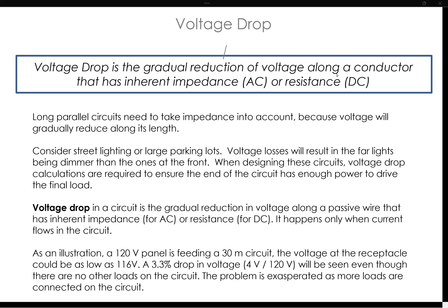Consider large parking lots, street lighting, or ballparks. These voltage losses — this voltage drop — is going to result in those lights that are really far away being dimmer than the ones at the front of that parking lot. So when you design these circuits, you need to calculate the necessary voltage drop and make sure that it's not too significant.